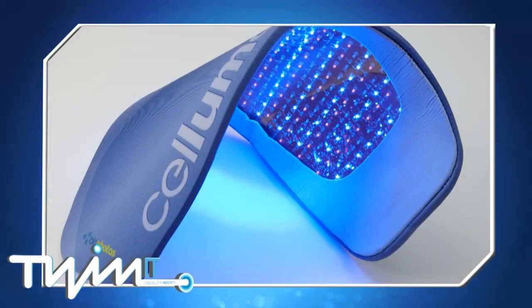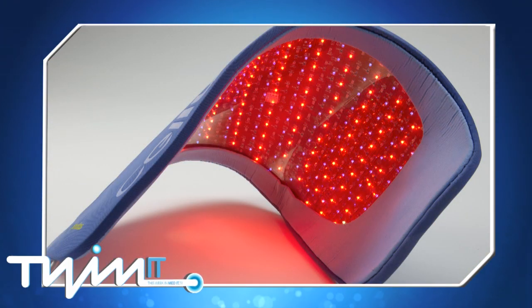The Celluma essentially has three programs that are blue, red, and infrared dominant, depending upon the desired depth of penetration of the light energy and accordingly the area of the body and the condition being managed. All three wavelengths of light are present in all three programs, but depending upon whether you're wanting to address conditions at the surface of the skin, directly below the surface, or as deep as 25 millimeters below the surface in muscles and joints, that will determine what program you'll use and the dominance of light in that specific program.